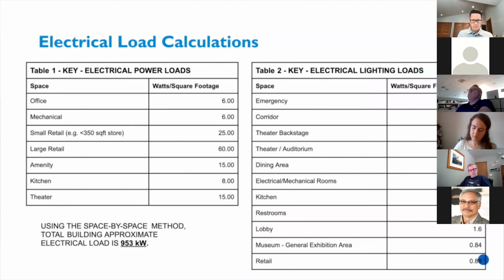To calculate the total electrical load our building would require, we use the space-by-space method. This categorizes the typical watts per square footage for different types of spaces, shown in two tables: Table 1 for electrical power load, and Table 2 for electrical lighting load.